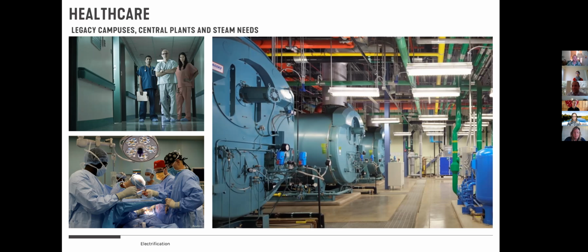We can do medical office buildings standalone. They're actually not complex at all, but it's the large scale healthcare environments, the OSHPD-1 hospitals, that typically have been tied to these legacy central plants. And so getting new ones often means developing a plan to transition the project off of gas. There are still some systems though that I would say are still best served by a gas system. And typically that is around sterilization. So if they have a large throughput requirement for sterilization, it is hard to find a cost-effective steam generator that's all electric right now that serves high throughput sterilization requirements.